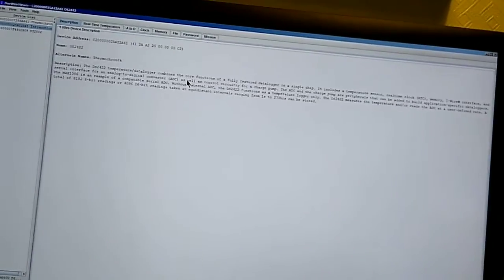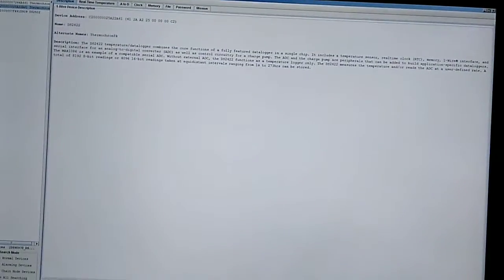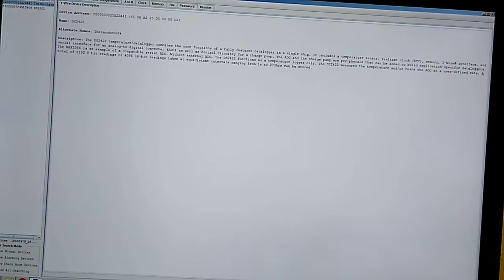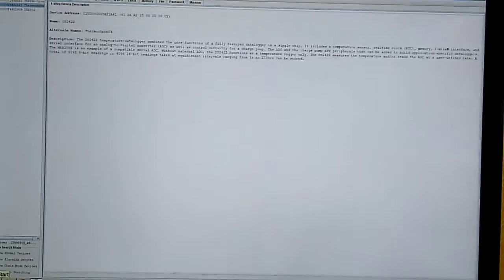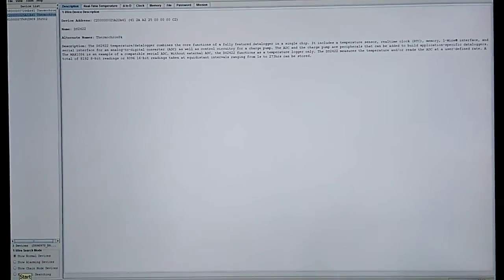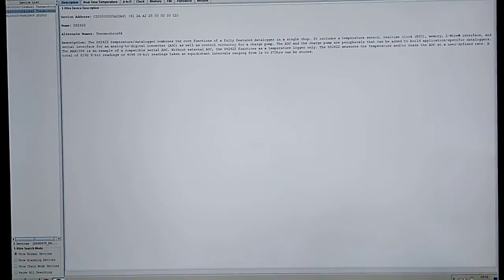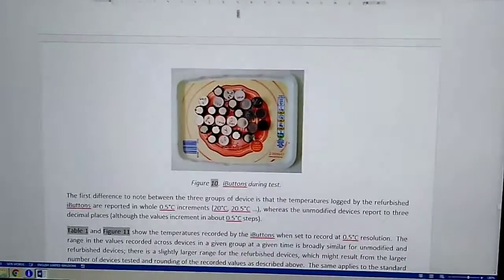So I did some tests on the i-buttons. I had a sample of about 10 of the refurbished ones, some new DS1922s and some older 1922s, just to see how badly not having the calibration data affects the temperature accuracy of the device.